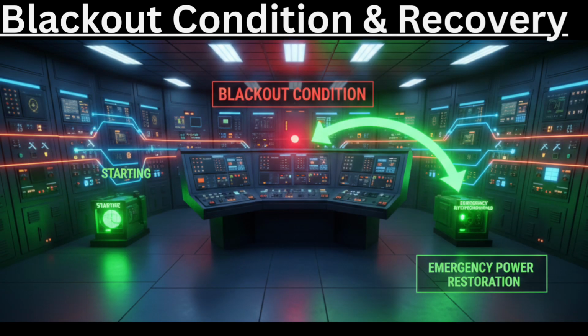Blackout condition or recovery. A blackout means complete loss of electrical power on the ship. This may happen due to generator trip, overload, fuel failure, or protection relay operation. When blackout occurs, the emergency generator starts automatically within seconds. The emergency switchboard supplies essential loads such as steering gear, navigation lights, communication systems, and emergency pumps.